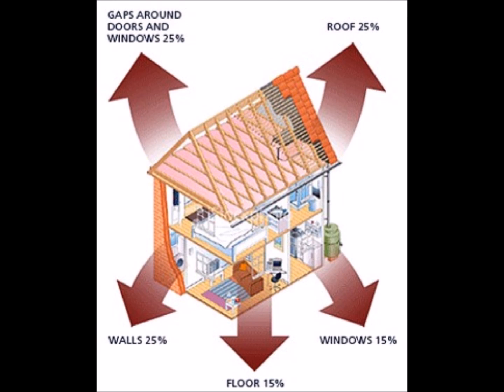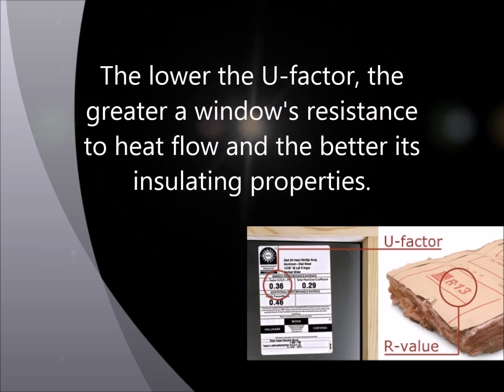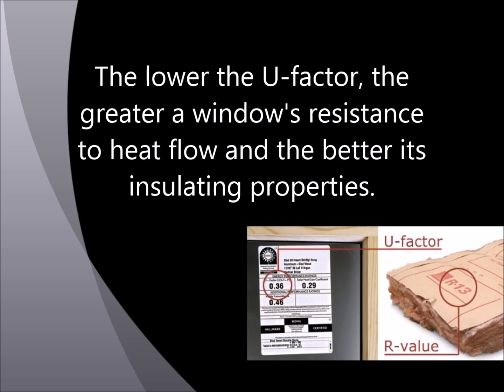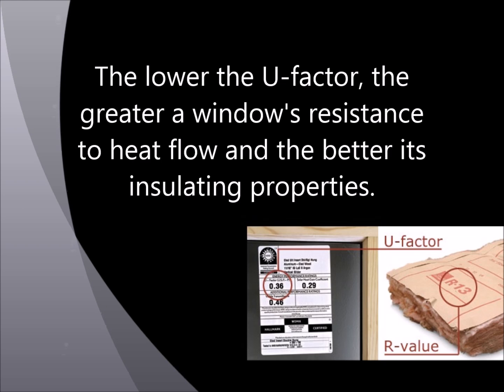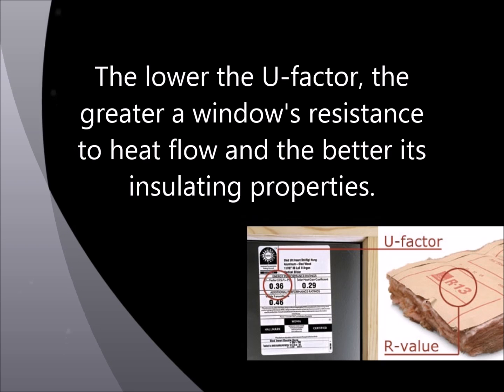The rate of heat loss is indicated in terms of the U-Factor or the U-Value of a window assembly. The lower the U-Factor, the greater a window's resistance to heat flow and the better its insulating properties. The nationally recognized rating method by the National Fenestration Rating Council or the NFRC is for the whole window, including glazing, frame, and spacers.